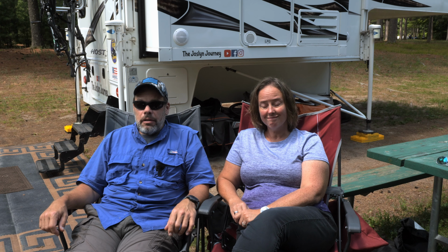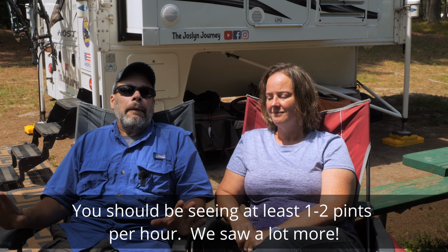The second part is kind of funny. You end up opening up all your windows and your doors. You're trying to see if that air conditioning unit will stay on for an entire hour without cycling. We performed this test, and it continued to run for that entire hour and literally poured moisture off the roof.